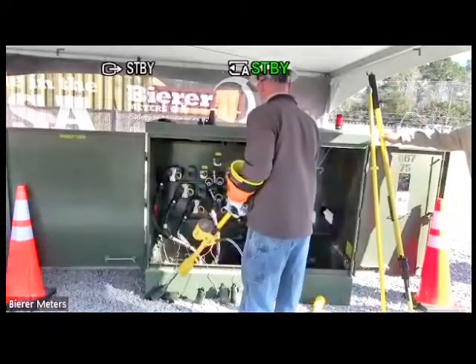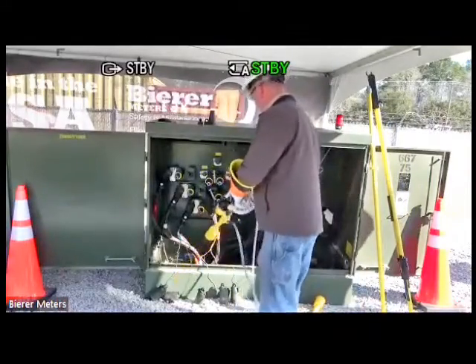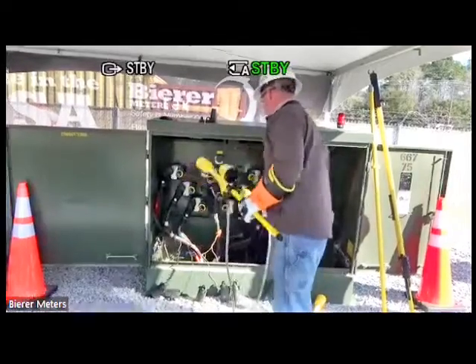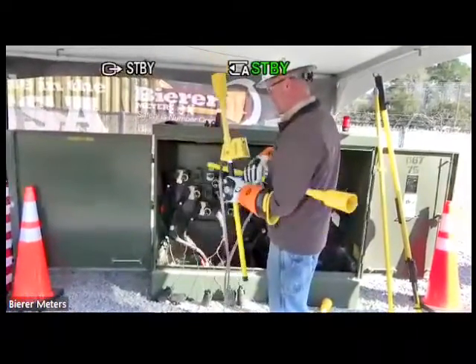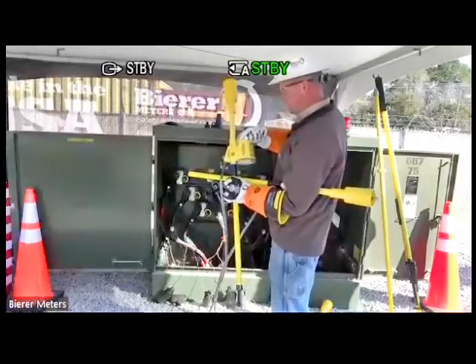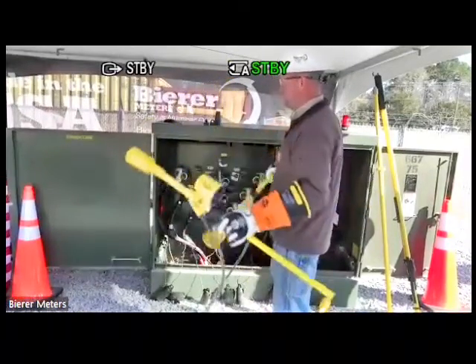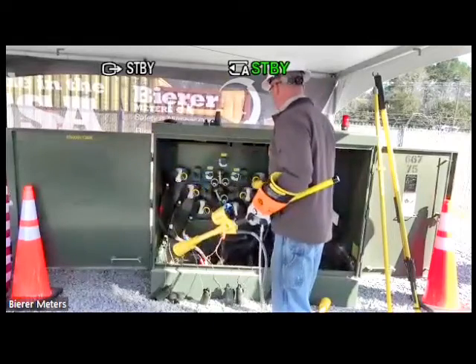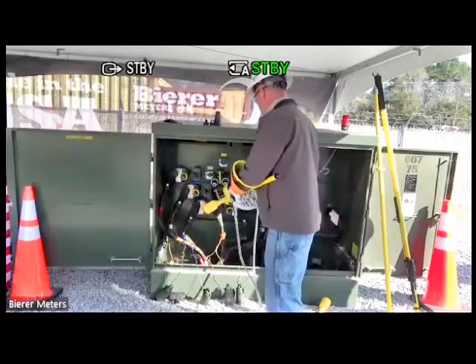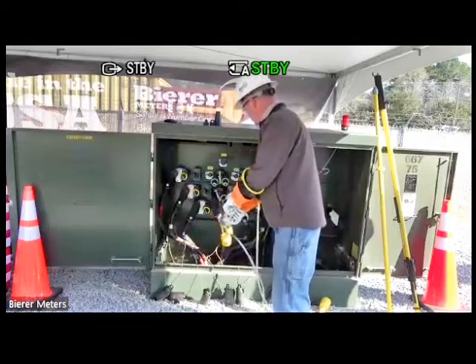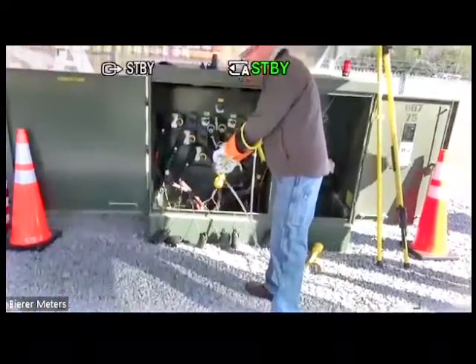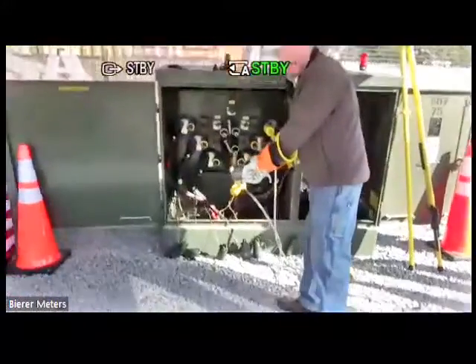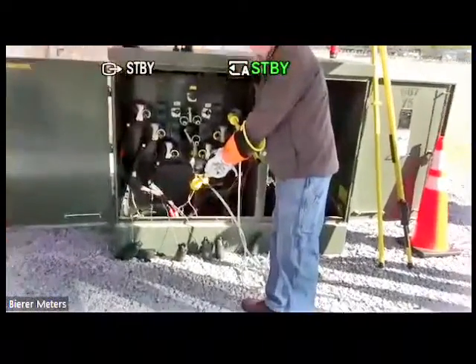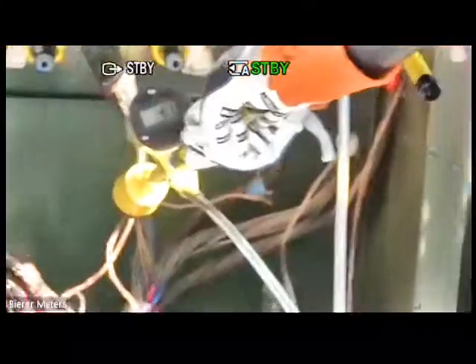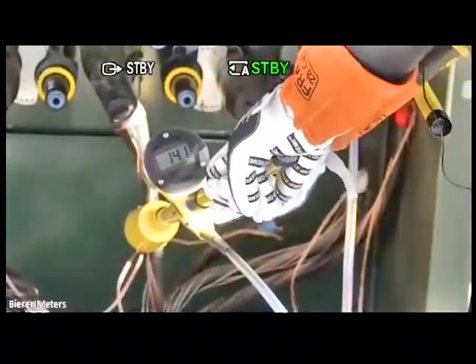So if I go phase to ground here, about to do it on the wrong switch position because I already saw my 1. And since I am going to do phase to phase out of phase, remember this is 23.8, 23.9 roughly phase to phase. So I have to put it in the 25 kV switch position. But my phase to ground readings, so here's my 14,100. Get Ryan to zoom in on that, just so you guys can see that number. So 14,100.